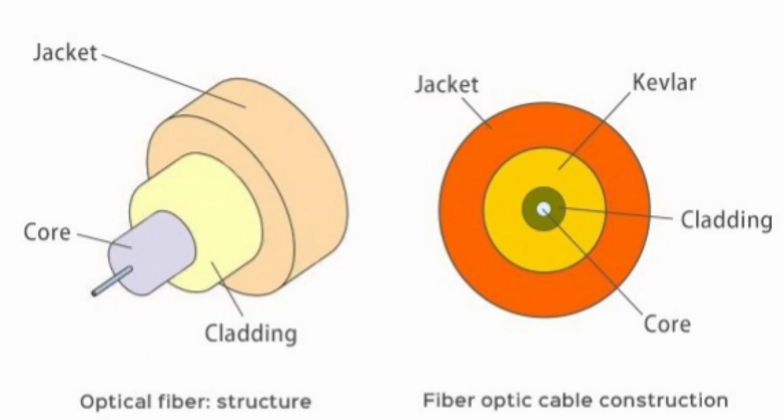But basically the easy way to resolve that is if you have an outside rated cable and you need to run it indoors, say 200 foot inside of a building, just use a splice box to convert to an inside rated cable. So you just take your cable straight in, down the first wall or somewhere like that, put it in a splice box, splice it, put in a bulkhead connector, and then just convert to an inside rated jumper and run that across the facility.